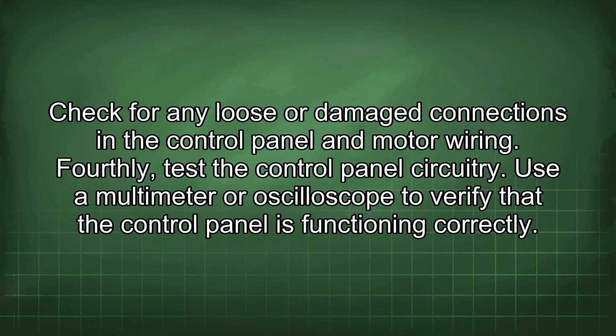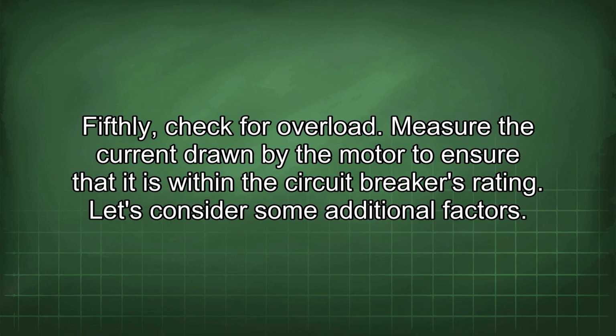Fourthly, test the control panel circuitry. Use a multimeter or oscilloscope to verify that the control panel is functioning correctly. Fifthly, check for overload. Measure the current drawn by the motor to ensure that it is within the circuit breaker's rating. Let's consider some additional factors.